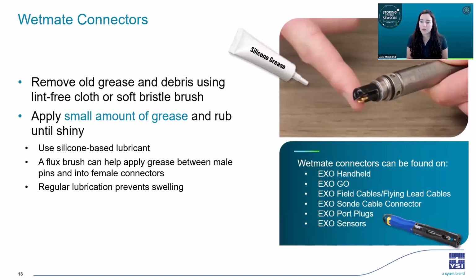And you can use a flux brush, like I mentioned earlier, or another small brush to help you get between the pins. And then always clean and lubricate your sensors before reinstalling them in your instrument, or putting a plug back in. That's because wet mate connectors like to be moist and not dry. And with just that regular cleaning and lubrication, about once a quarter or so, it'll help prevent the swelling and maintain your connectors for a long, long time.